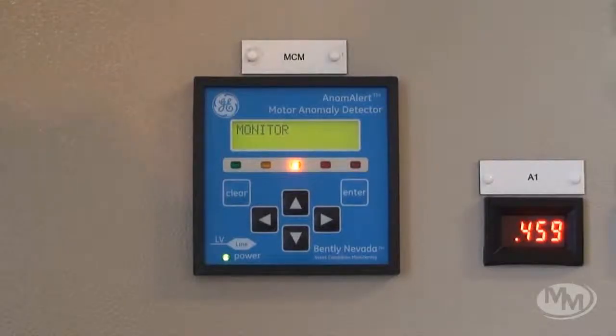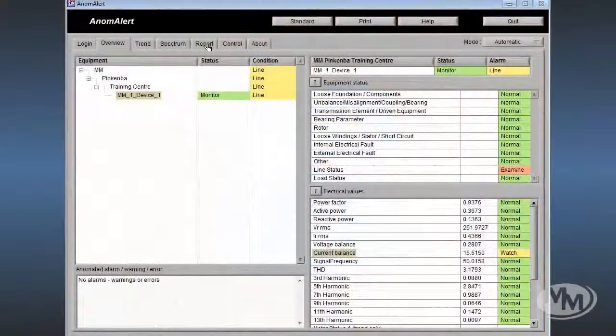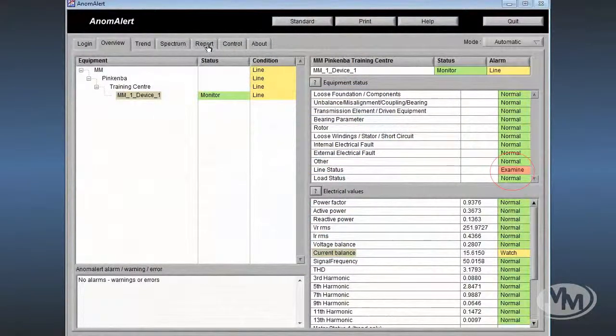Here we can see the Anomalert unit is now indicating an alarm. This is due to the previously introduced fault having met the Anomalert persistence criteria and being elevated to an alarm condition.